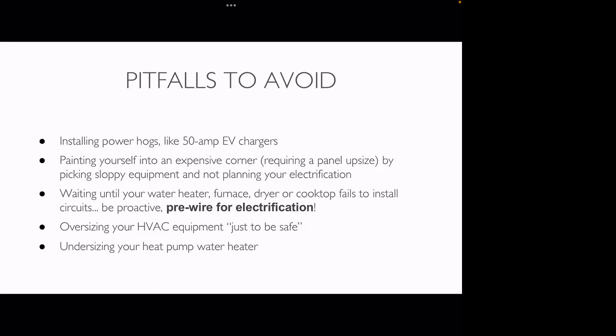One other pitfall to avoid is oversizing your HVAC equipment. A lot of HVAC installers do this because they don't want a callback from someone who's a little chilly on the coldest day of the year. So they oversize the systems, and you just end up paying a lot more than you need to, and the systems can be less efficient when they're oversized.